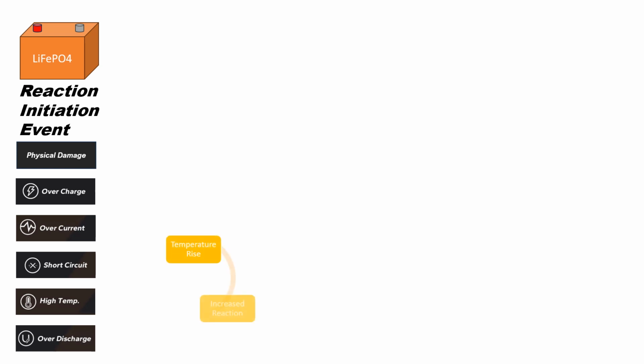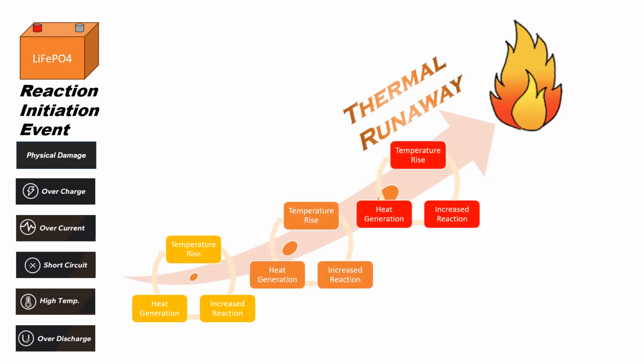All of these things can lead to a reaction initiation event, which causes increased reaction inside the cells of the battery. That increased reaction, as you may remember from chemistry, means the molecules get more active and create heat generation. That heat generation causes temperature rise, and as the temperature goes up, you get increased reaction. It becomes a cycle, and if it's not controlled, you can end up with what's called thermal runaway, where the temperature rises exponentially until it all catches fire.